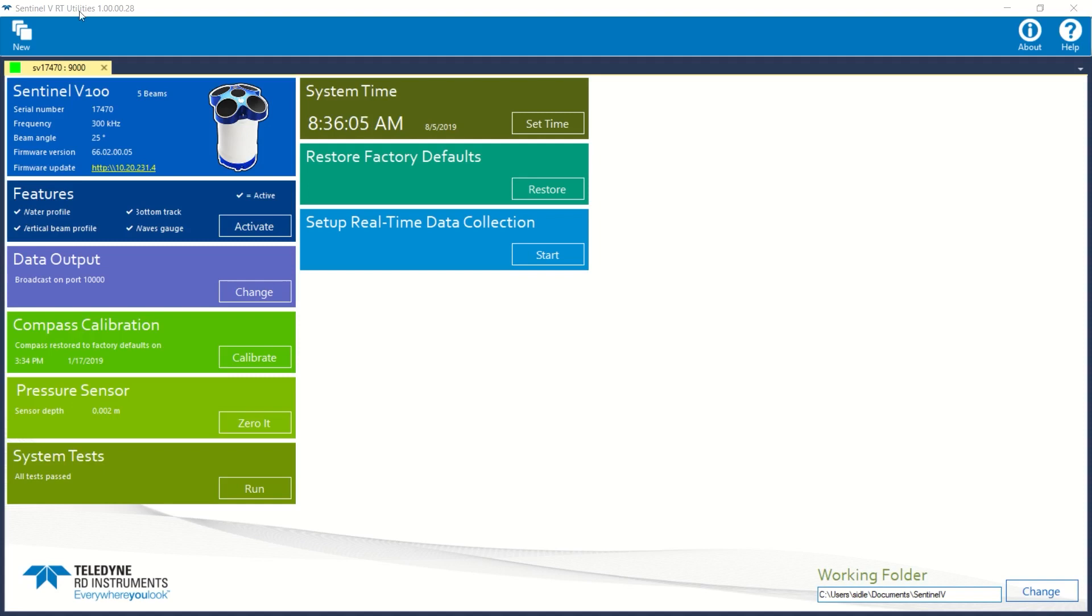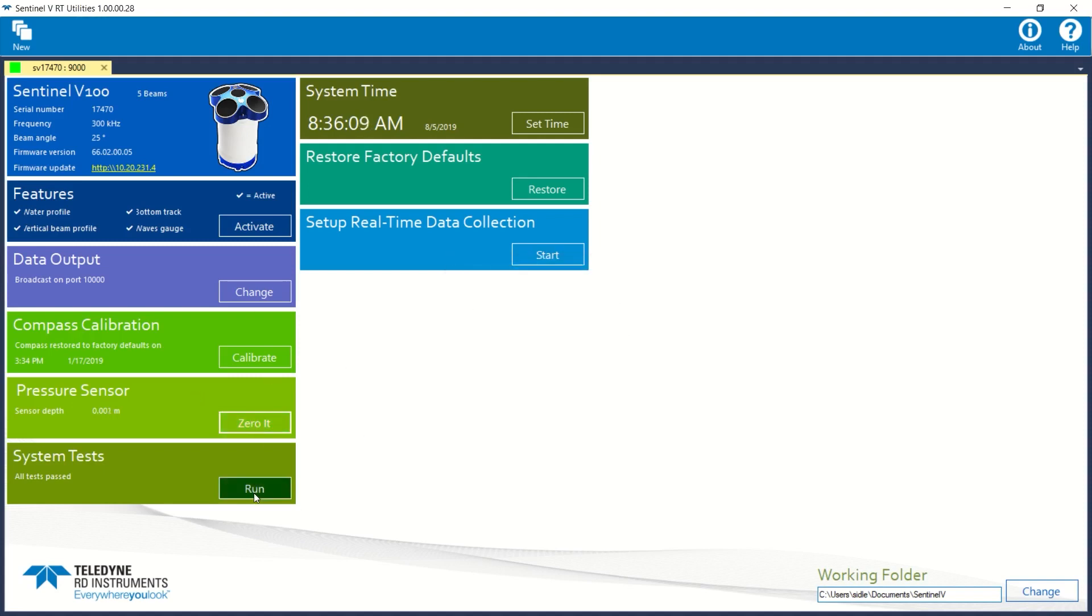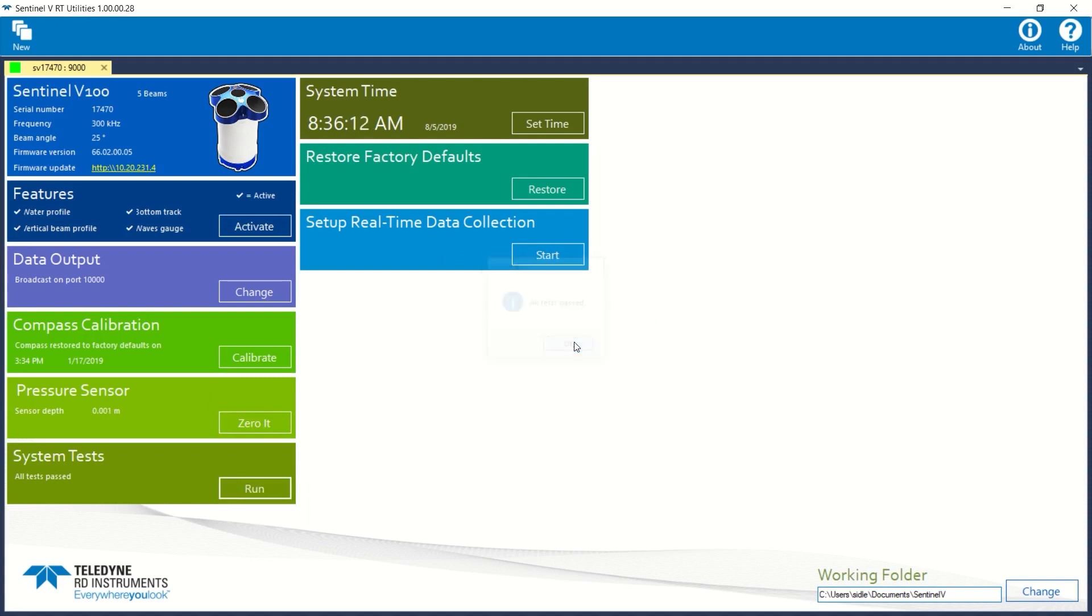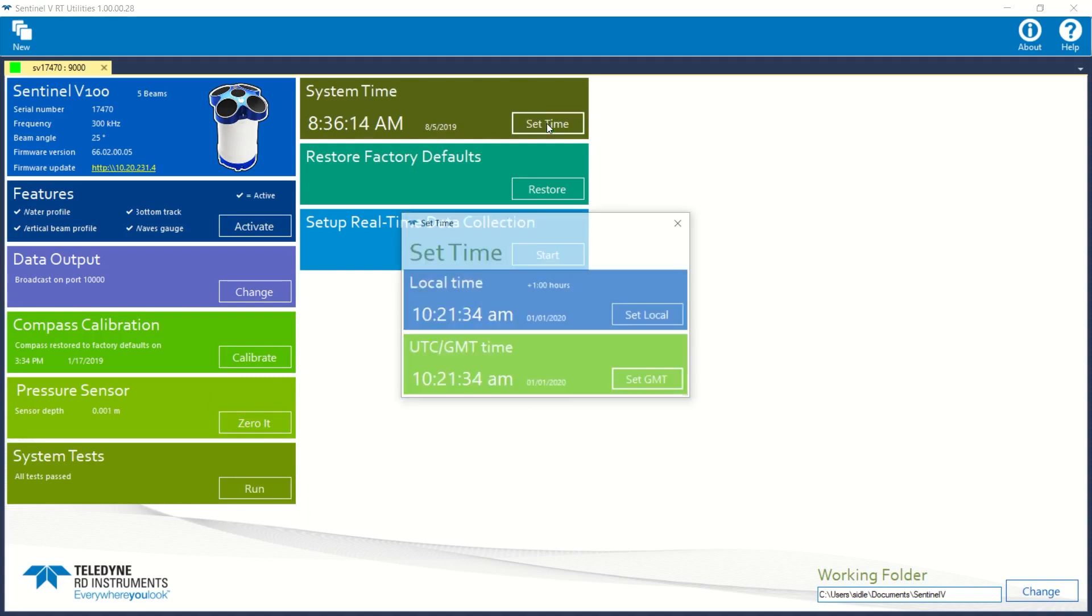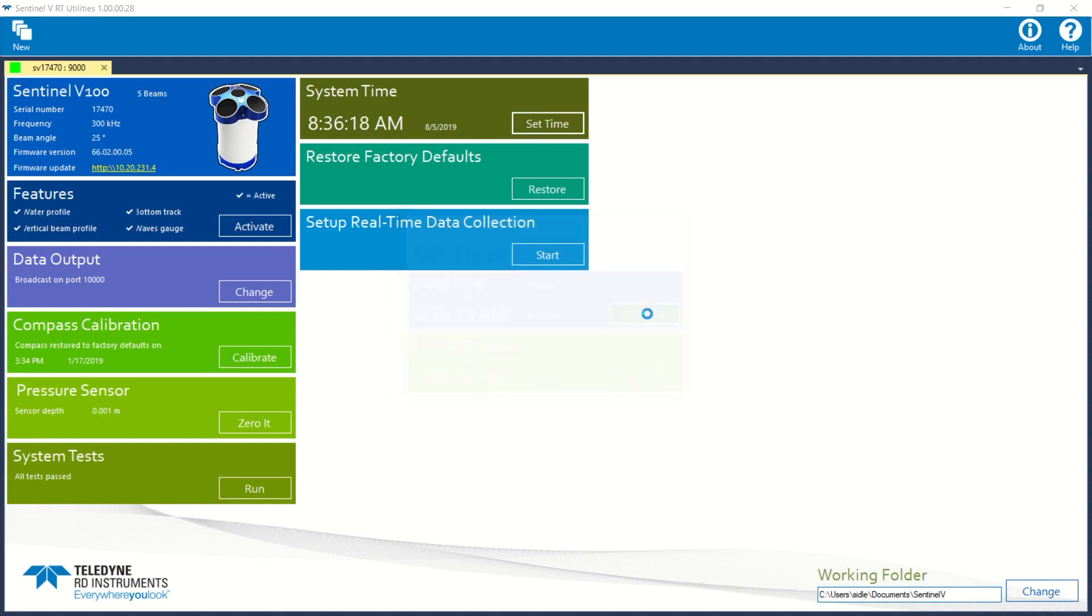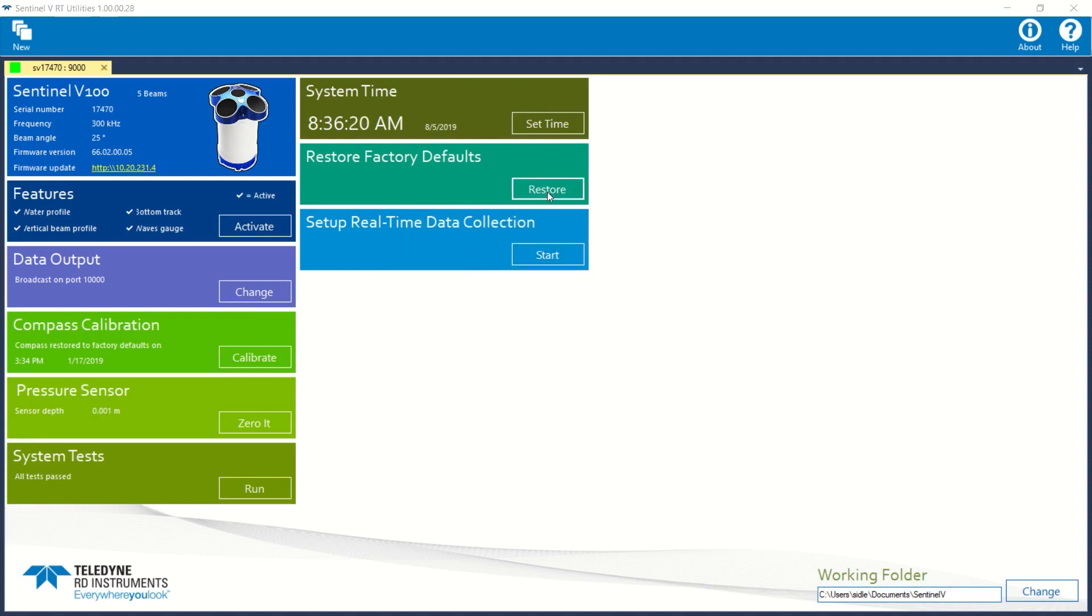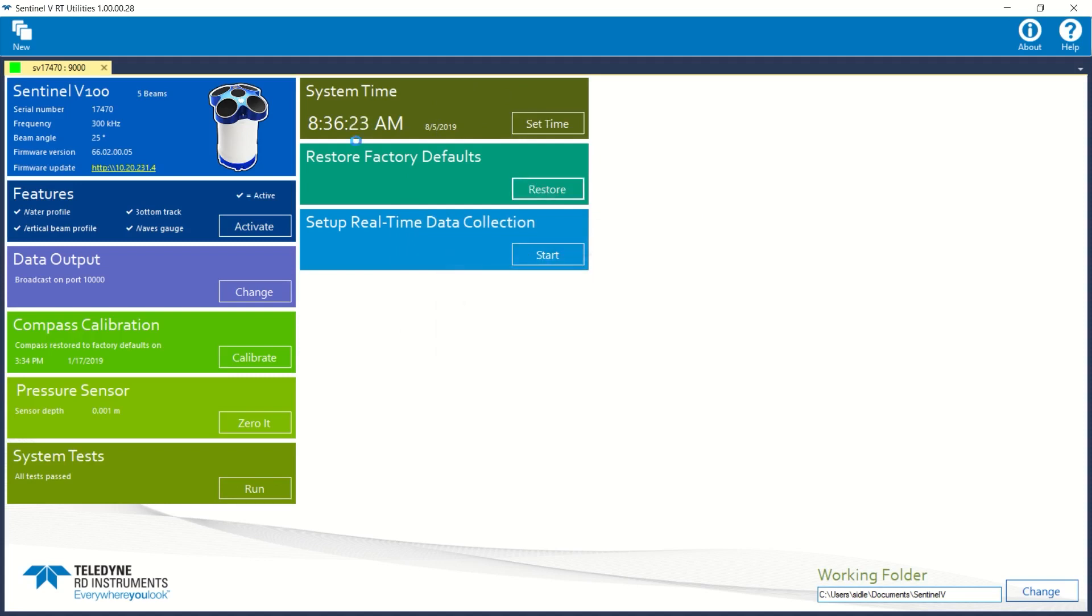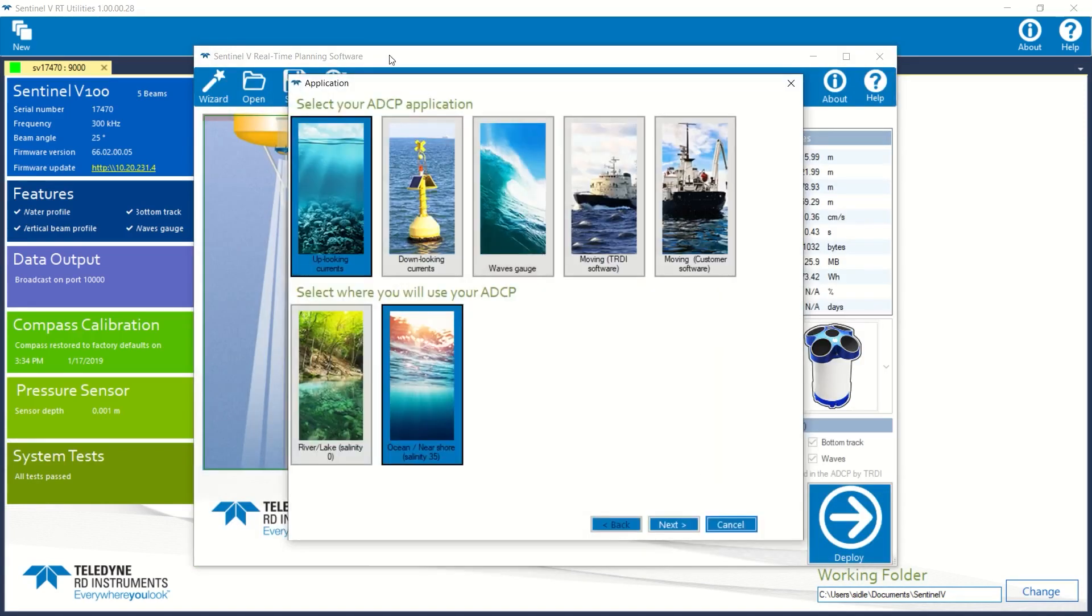I'll go ahead and zero the pressure sensor, run the system test. I'm going to set my time to my local PC time, restore the defaults, and start the setup of real-time data application.